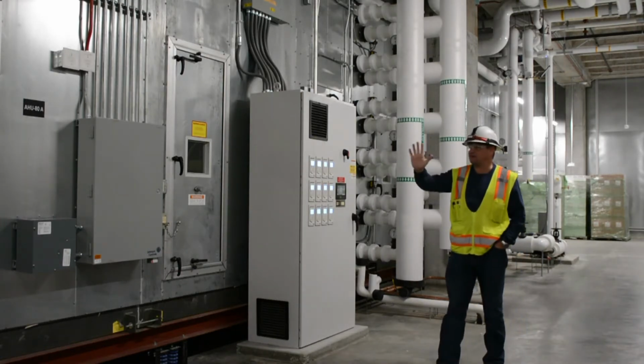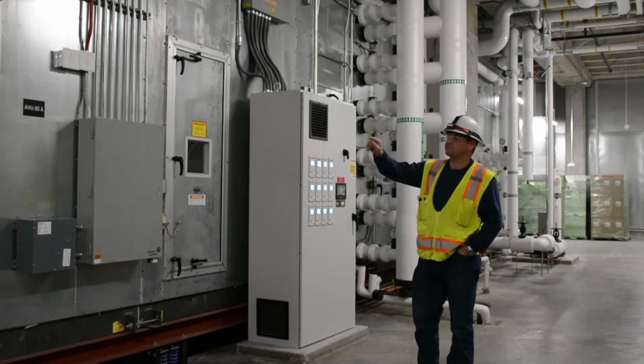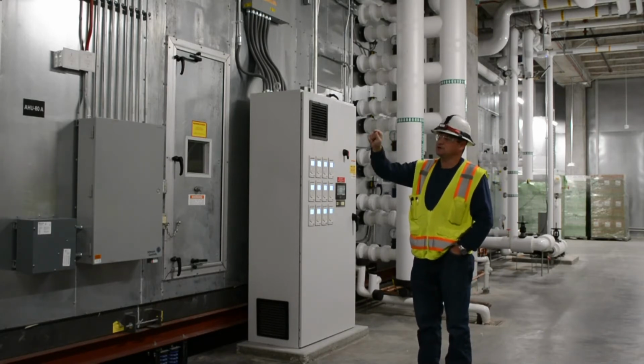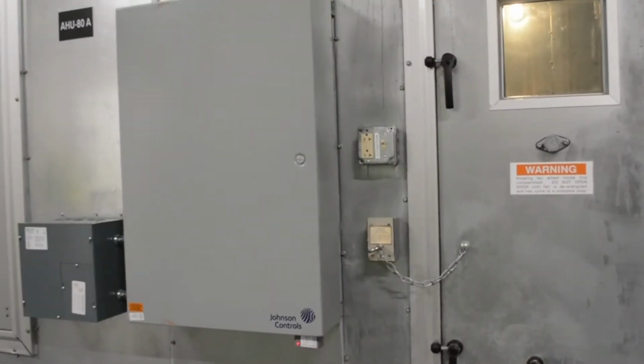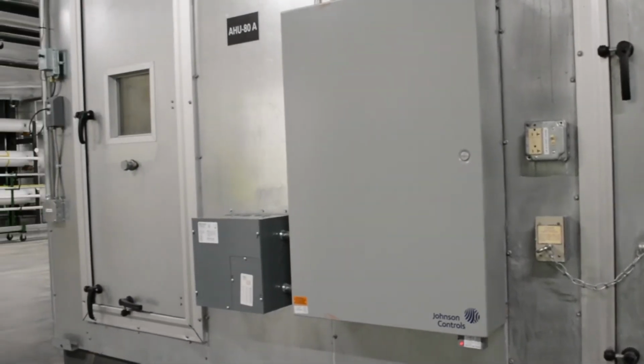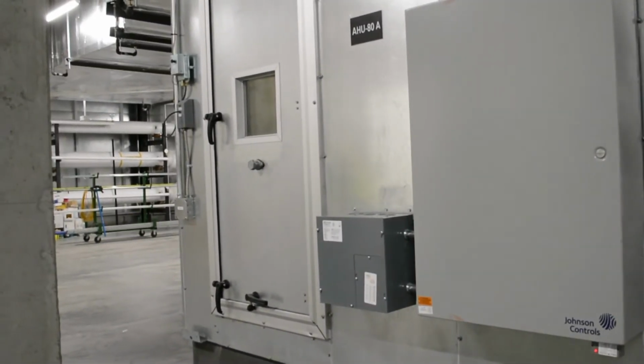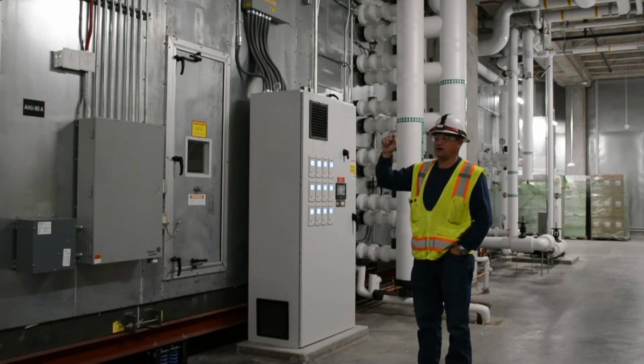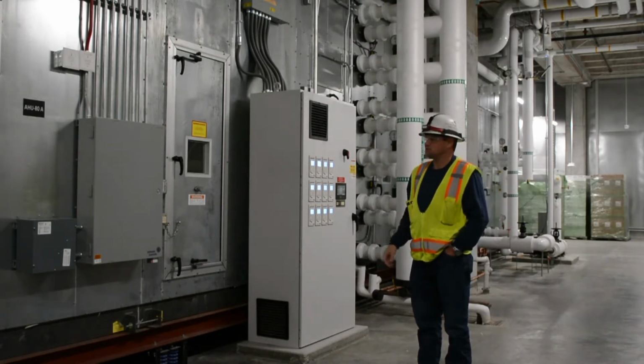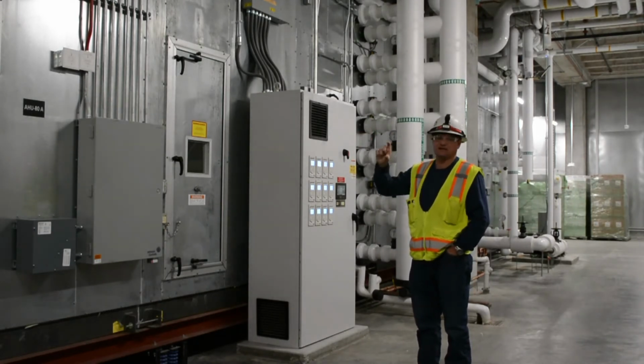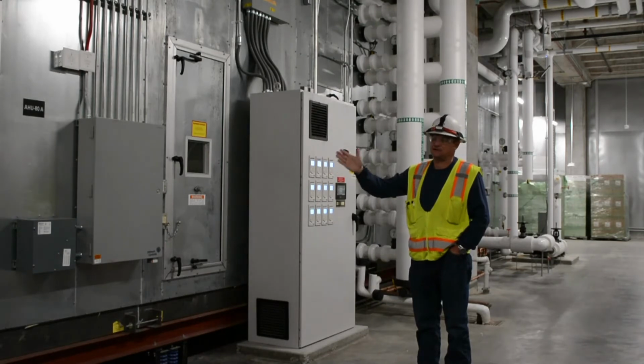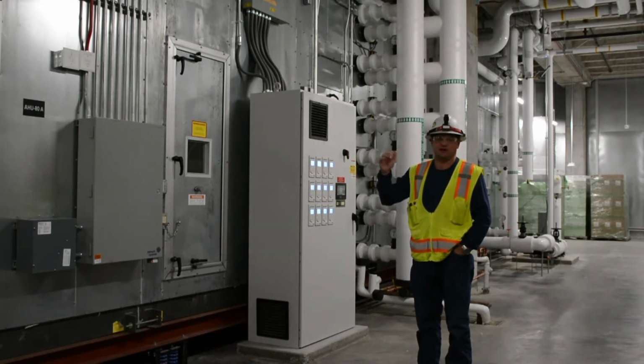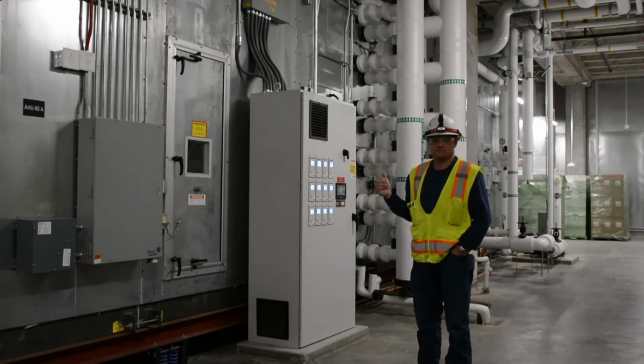After that, you have your leaving air section. Here we have some safeties of high duct pressure, your high duct pressure limiter, and those are items that could potentially shut the machine down in the event there is a failure of a damper downstream in the duct and the pressure increases rapidly. That's there to protect the ductwork. So that would be another item that if the machine is off, you'll get an alarm from Metasys and it'll tell you that we are off on high static. You're going to have to find the problem, correct it, reset it, and see if you've got stable operation after that.